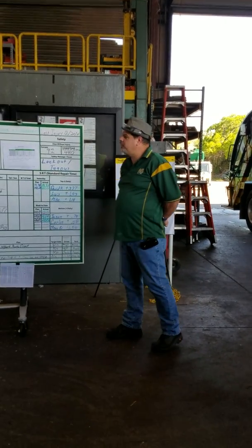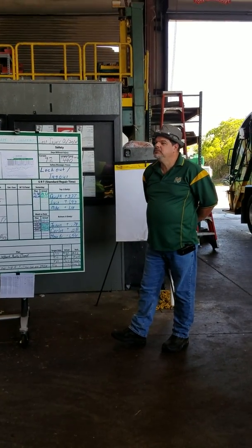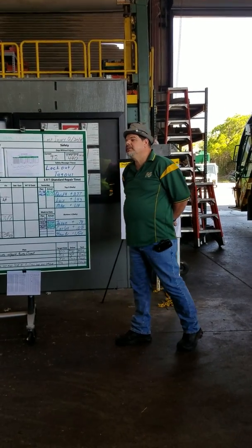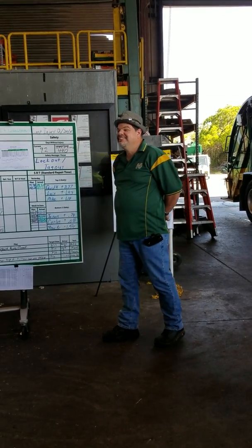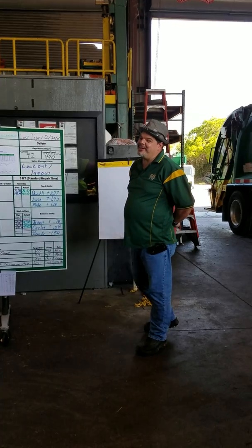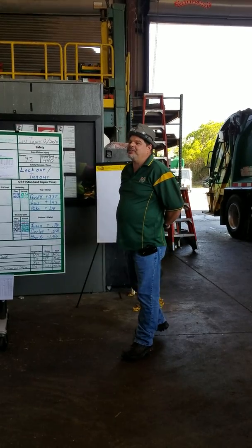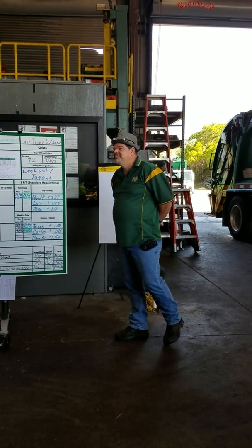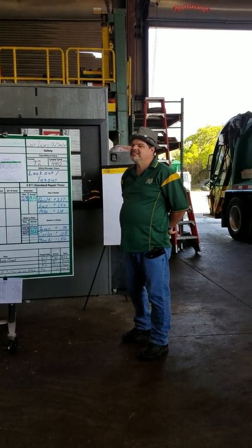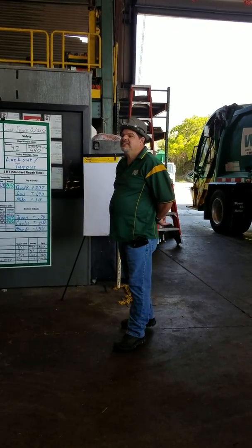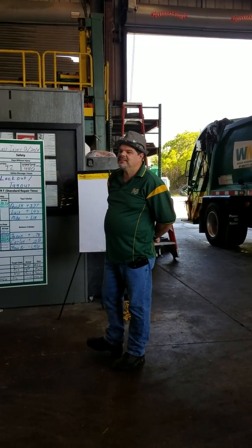So, what were some of the things brought up yesterday? Cold leaks versus hot leaks versus pressure leaks. That's what you wanted them to bring up. That's what we should have brought up, I heard, but we didn't. So tell me about cold leaks. Cold leaks are when the truck is cold and there's no pressure on the system. It will leak, but once it heats up or is pressure tested, the leak stops. So we find no problem.